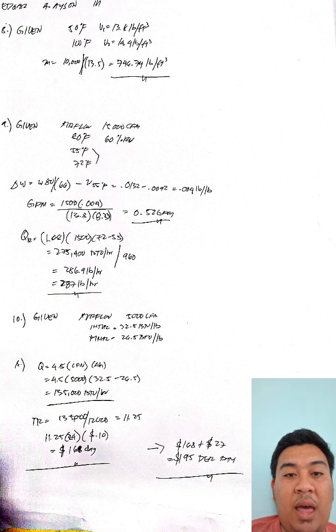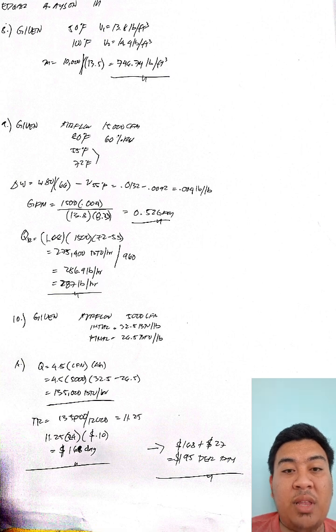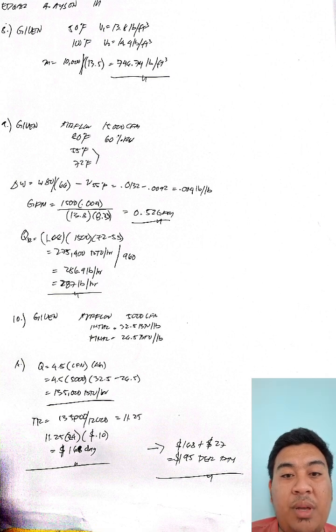For problem 9, a dehumidification system processes 15,000 CFM of air from 80 degree Fahrenheit with a relative humidity of 60%, then cools to 55 degree Fahrenheit saturated and reheats to 72 degree Fahrenheit. Using the formula GPM equals CFM times delta humidity ratio over specific volume times 8.33, calculate the rate of water removal in gallons per minute. Then for the second, if the heat stage uses a steam coil with a latent heat HFG of 960 BTU per pound, calculate the pounds of steam per hour required.